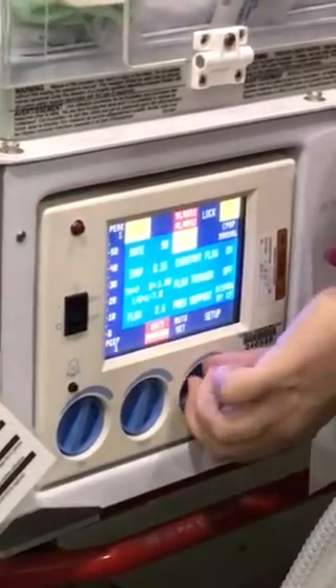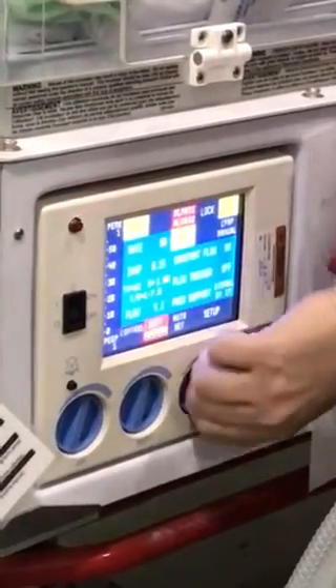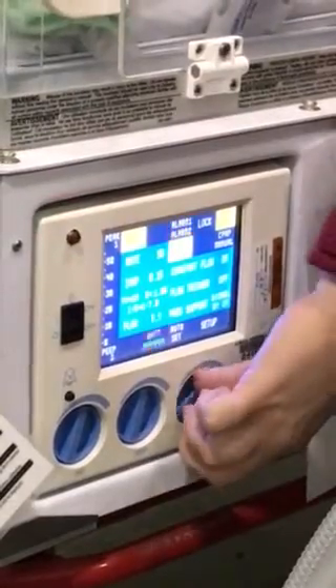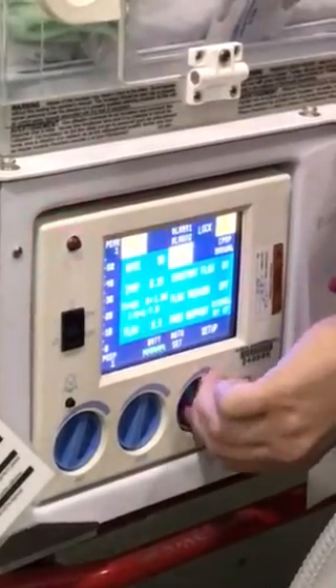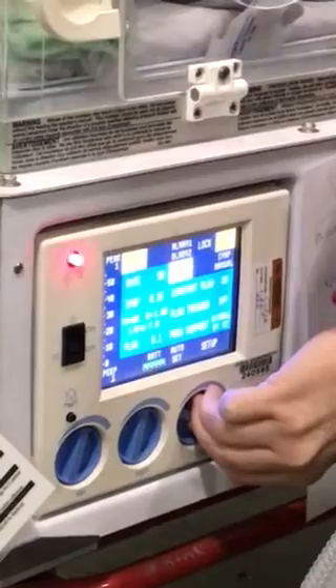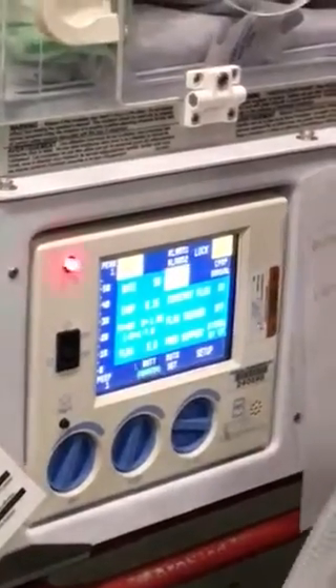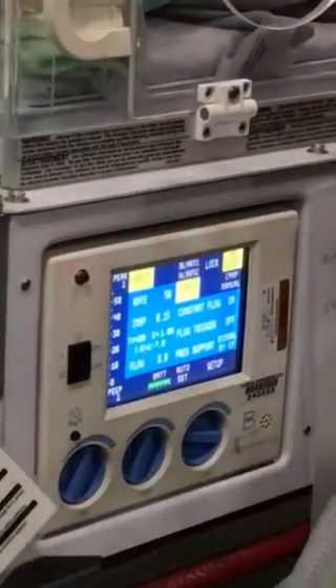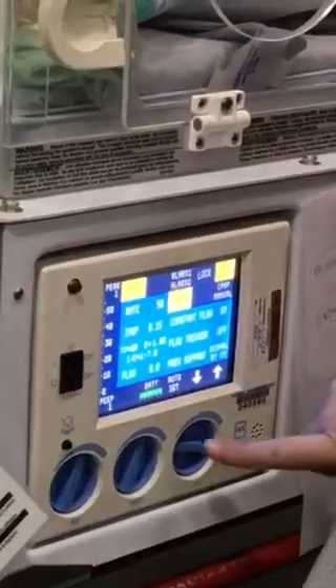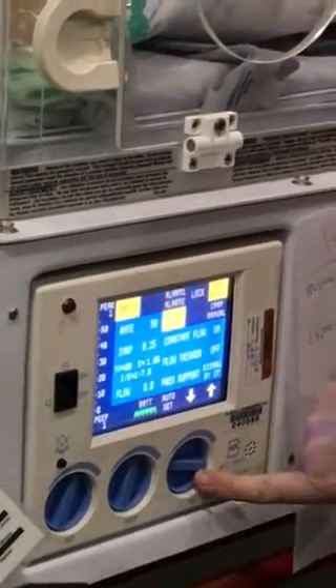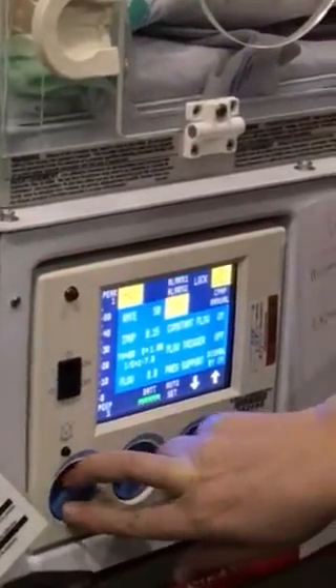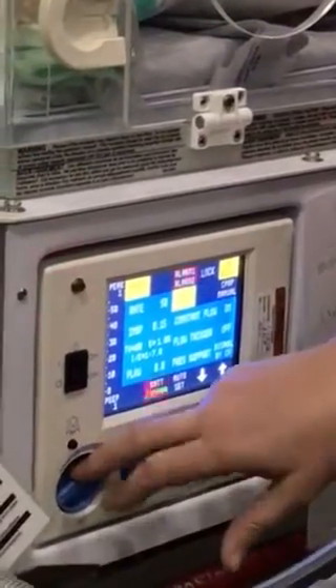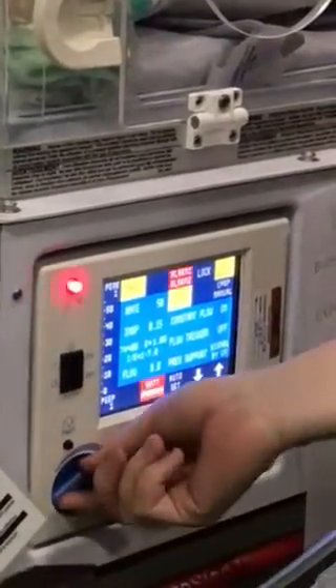A common mistake is people dial in the PEEP first, and then the PIP. It doesn't like that, and it'll alarm, and once it starts alarming, it'll default you out. So I wouldn't hit anything with alarms yet. I would put in your settings first. So you have a flow of 8. Then I go to your PIP, and a good starting place is always to set it up at 20/5, and then you can just tweak it from there.